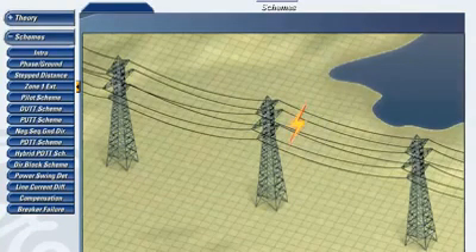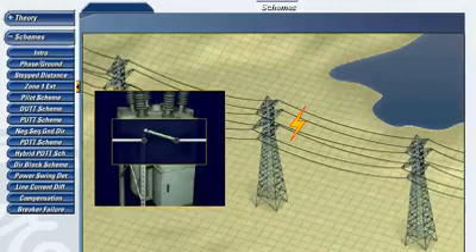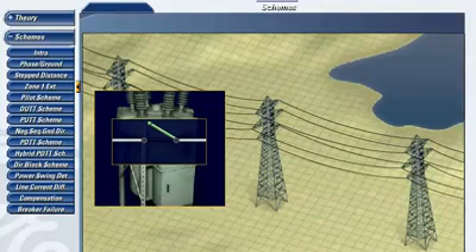If lightning strikes a transmission line, it ionizes the air, which reduces the resistance between the different phases of the line. This reduced resistance allows a path for current to flow, and hence creates a fault. Once the transmission line is tripped and the fault is cleared, the ionized air is removed and there no longer exists a path for current to flow. Closing the transmission line circuit breaker at this point would re-energize the line and transmission of power could resume.